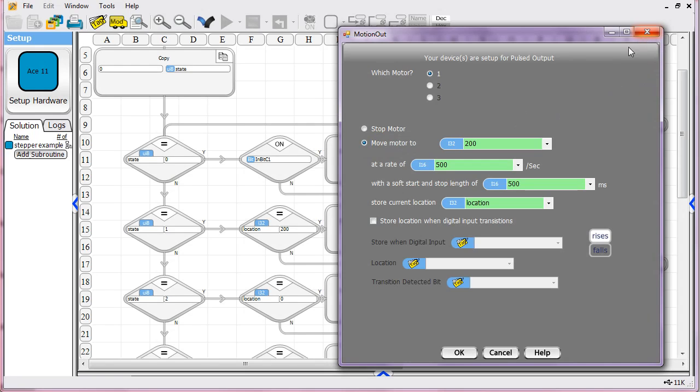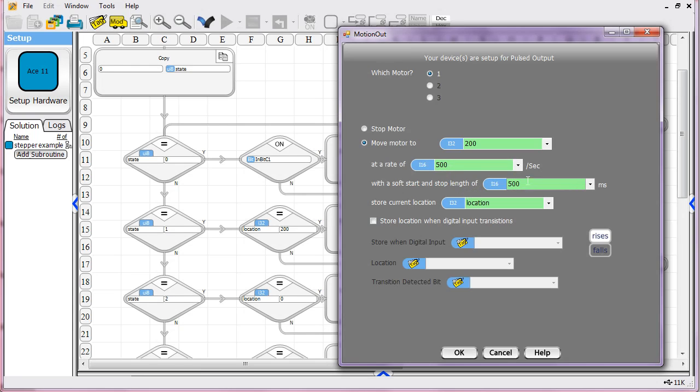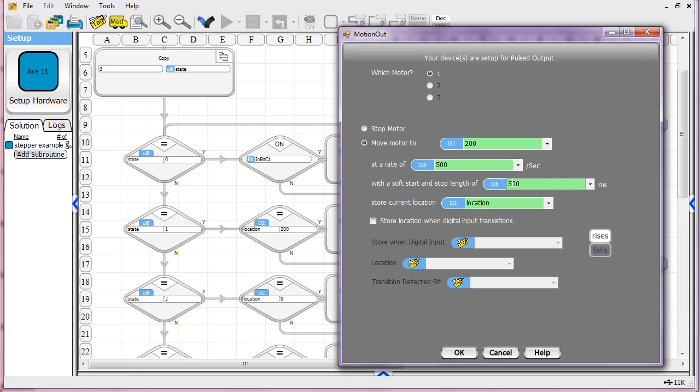The first motion, we're telling it to move to location 200. We're telling it how fast to move at a pace, in this case, of 500 pulses per second. We've got a soft start length. It says take 500 milliseconds to get up to this speed. Or if you're at speed, take that long to get back down to zero. Don't do it immediately at that speed. Ramp up and ramp down.